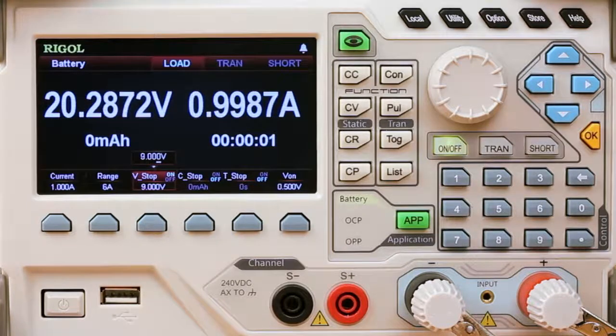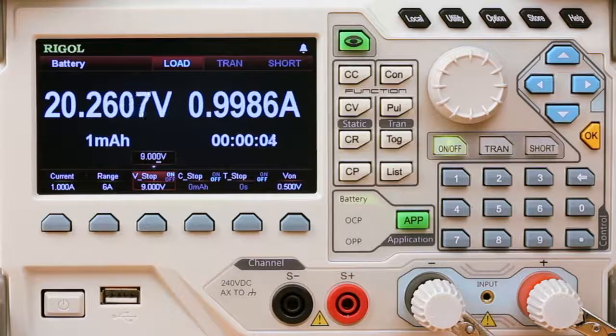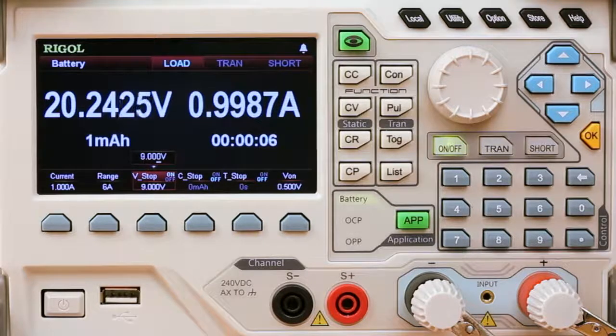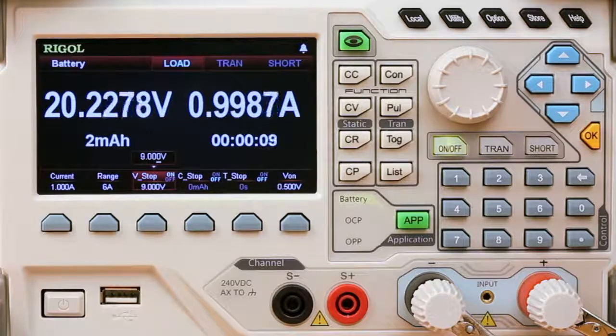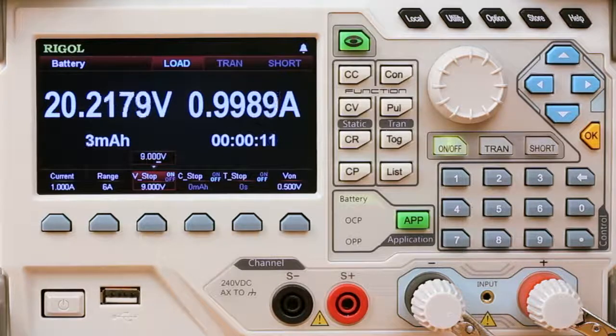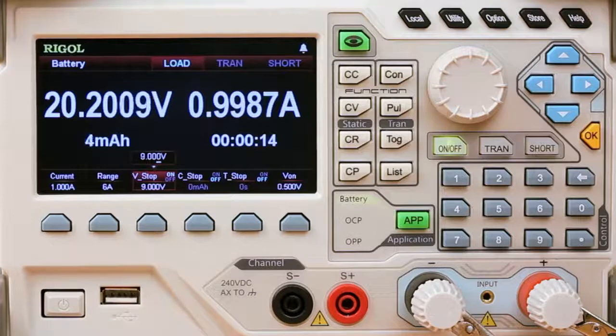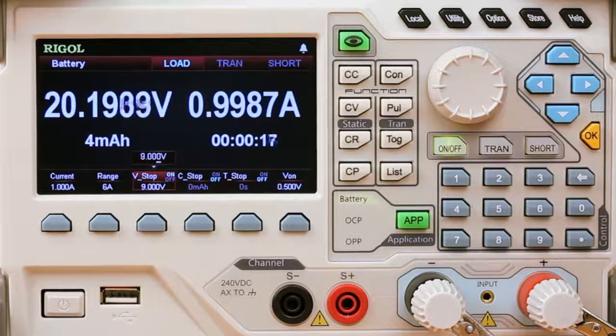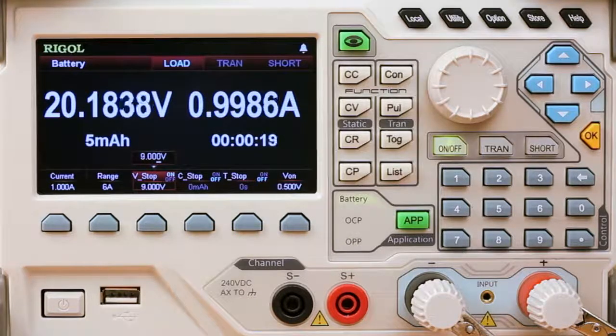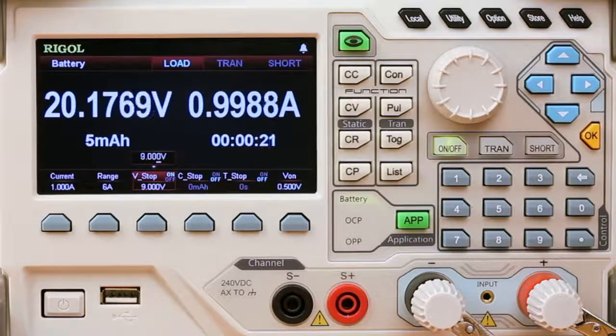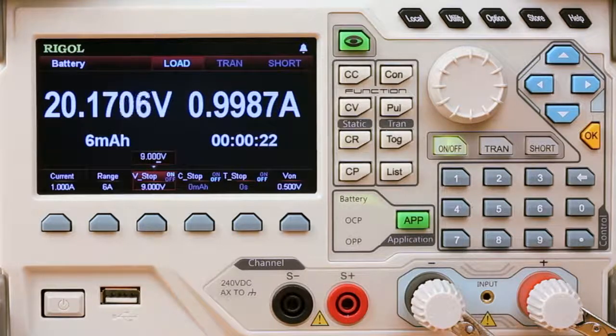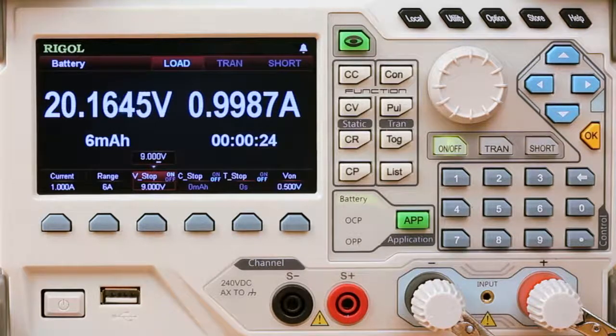So we see the current ramp up to 1 amp and the voltage will start to draw down. In real time we can also measure our capacity. Here we're going at about a milliamp hour every 3 or 4 seconds. And our timing as well is listed on the display. So these are all great values, important values for our battery test that we're going to record and use later when we're comparing results.